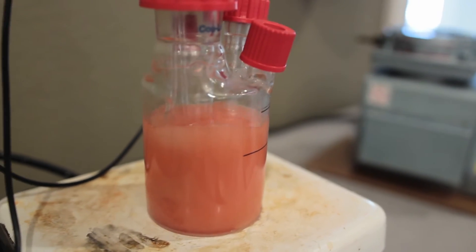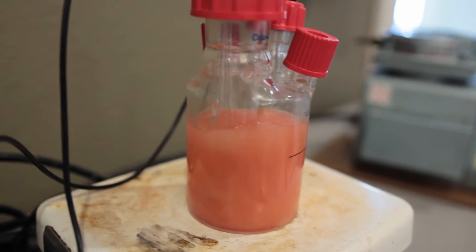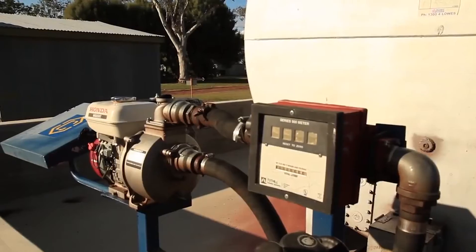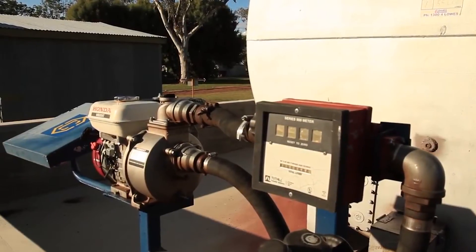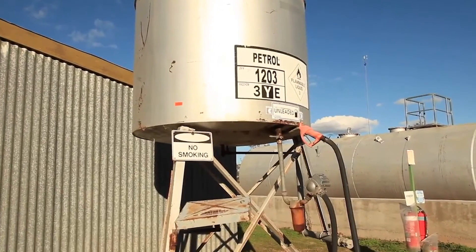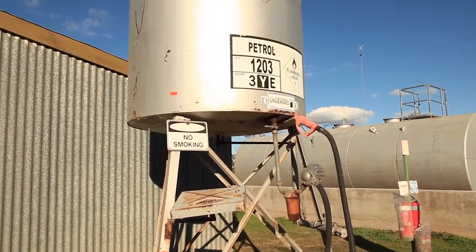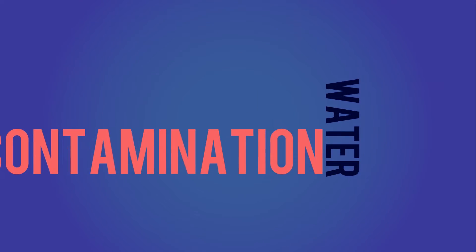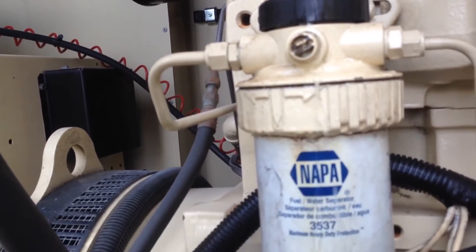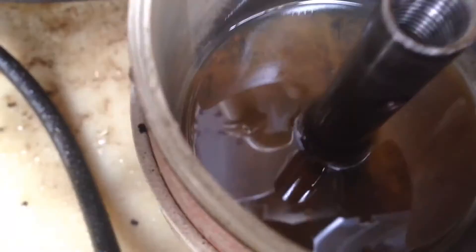Fuel that exceeds 500 parts per million puts your fuel and equipment at serious risk and requires immediate attention. Water contamination is one of the most common fail points in fuel.